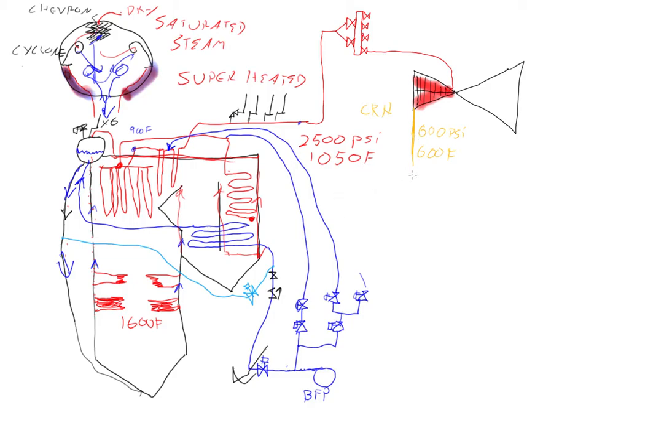So we can't afford to let this temperature get too low. We take this 600 degree steam and flow it over here. We got more coils here and the flue gas flows across these coils. The flue gas cools off, the steam heats up, and then we come out the other side as hot reheat.